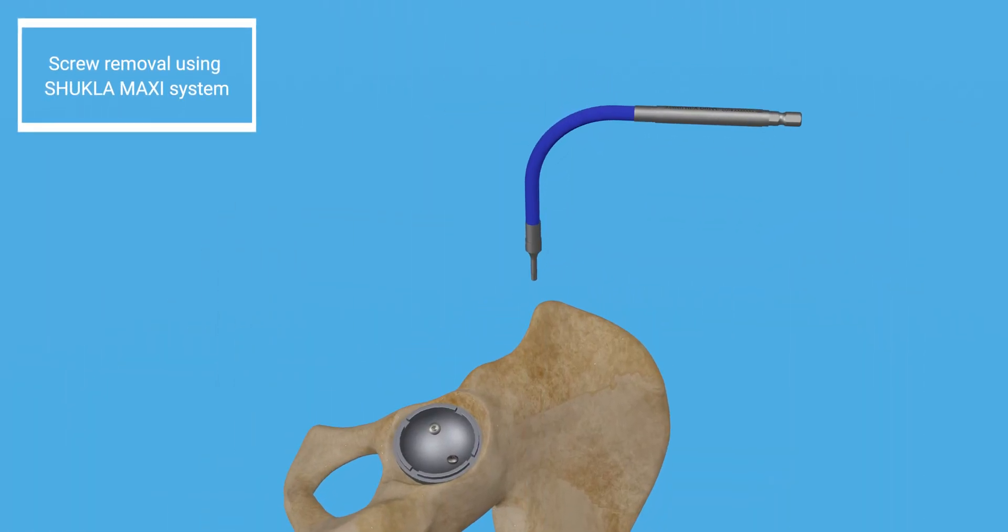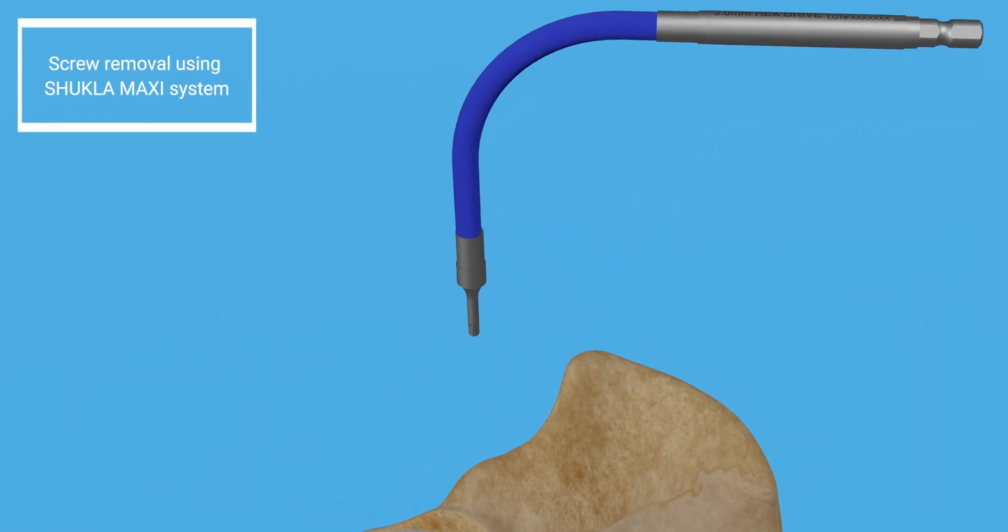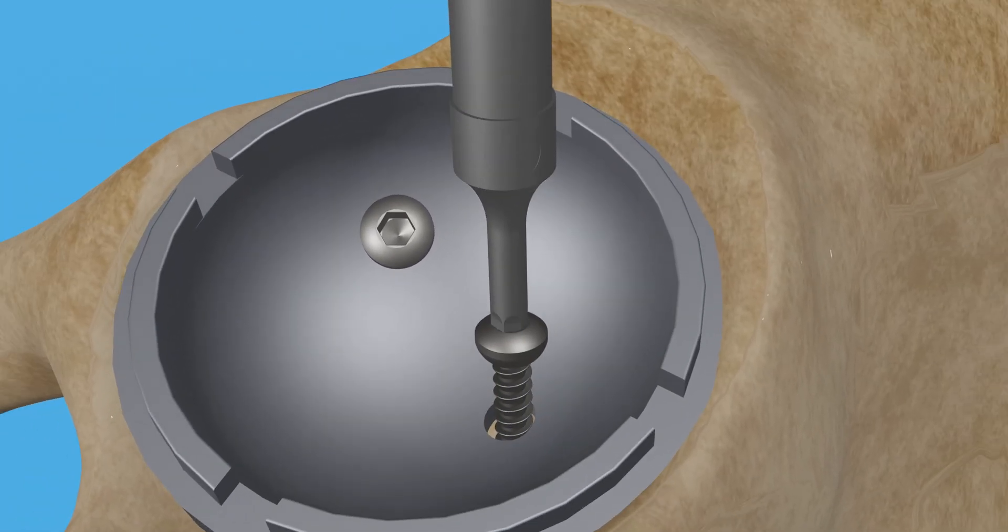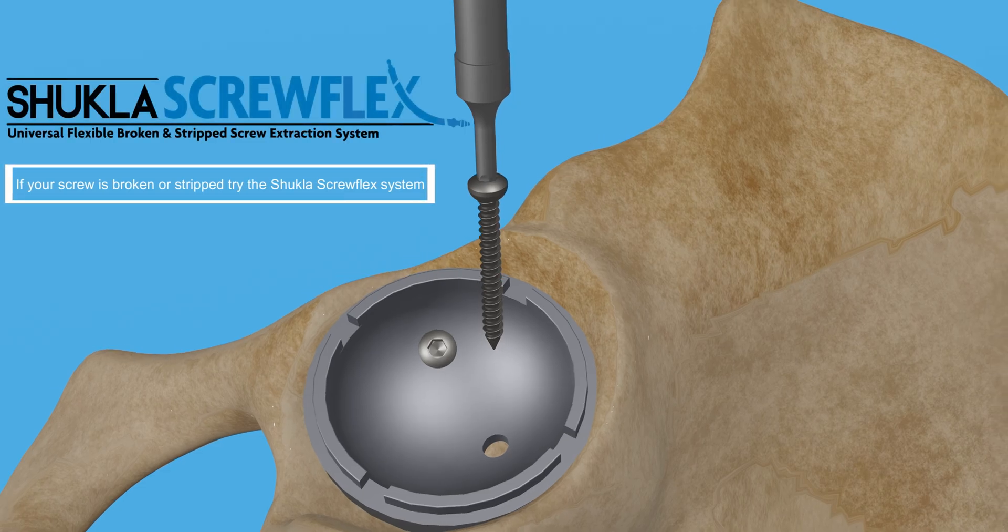Examine X-ray for cup screws. If screws are present, remove the poly and use the Shukla Maxi system to remove the screws. If the screws are broken or stripped, use the Shukla Screwflex system with flexible drivers for screw access.